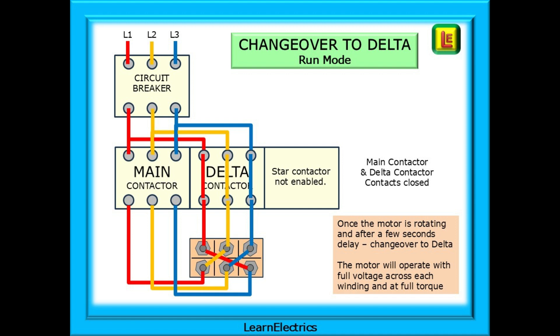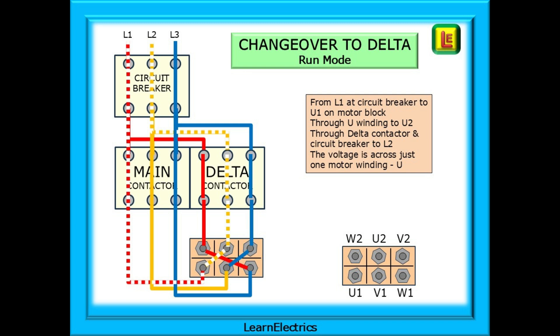Once the motor is rotating and after a few seconds delay, the contactors will change over to delta operation. The star contactor is disabled and the delta contactor comes into circuit along with the main contactor. The motor will operate with full voltage across each winding and at full torque. Follow the route from L1 and back to L2 at the distribution board. The flow is from L1 at the circuit breaker to terminal U1 on the motor block, through the U winding inside the motor to terminal U2, then through the delta contactor and circuit breaker to L2 at the distribution board. The voltage is now across just one motor winding, U in this example, and this happens in rotation with each winding U, V, and W.